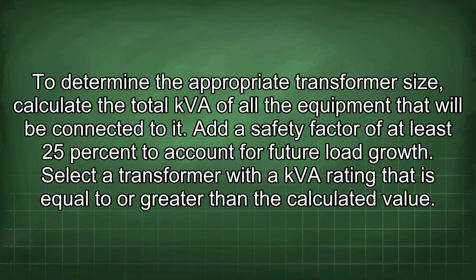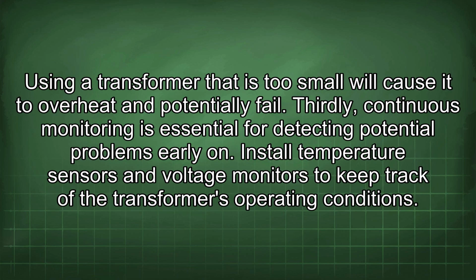To determine the appropriate transformer size, calculate the total kVA of all the equipment that will be connected to it. Add a safety factor of at least 25% to account for future load growth. Select a transformer with a kVA rating that is equal to or greater than the calculated value. Using a transformer that is too small will cause it to overheat and potentially fail.